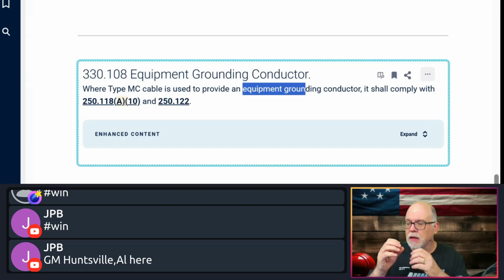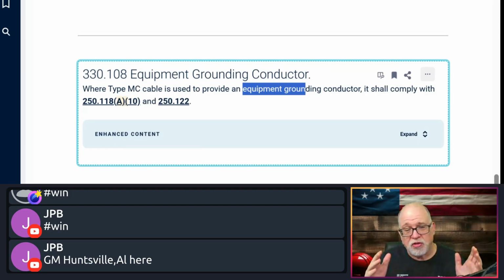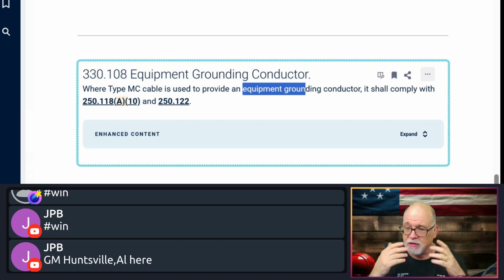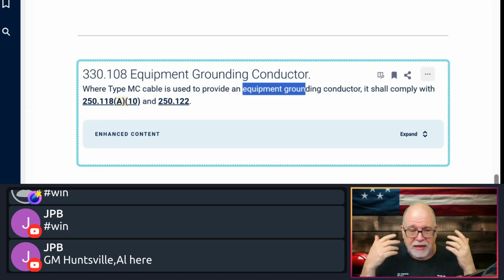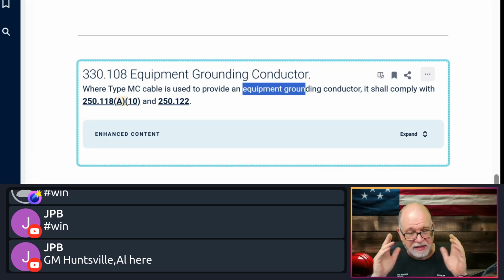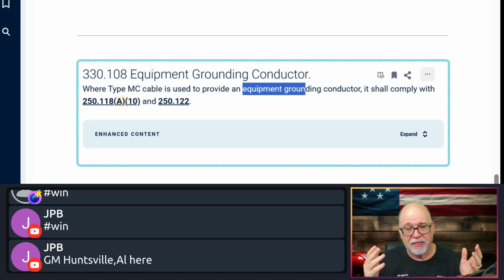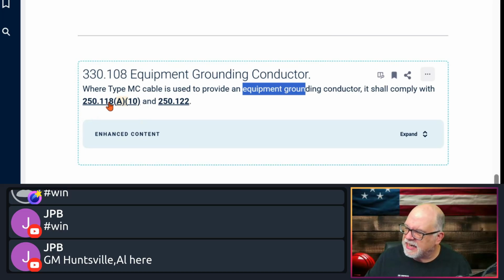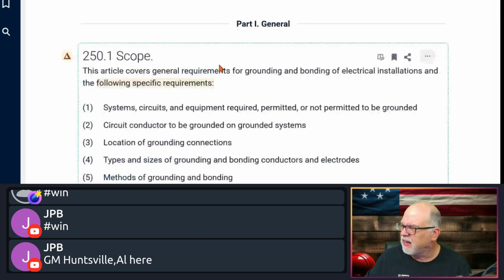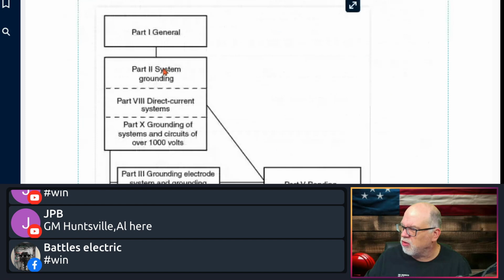So regular MC, you do not use the armor as an effective ground fault current path, although you still need to bond it. And that means using proper fittings that are listed, and you're required to do that anyway, terminating it properly, all that type of stuff. You still have to maintain the integrity of the path. Okay. And then of course, the 250.118(A)(10), I'll click on that. And again, that's just going to show you.